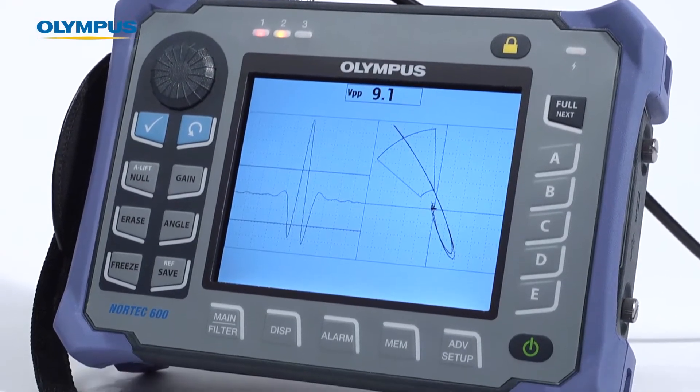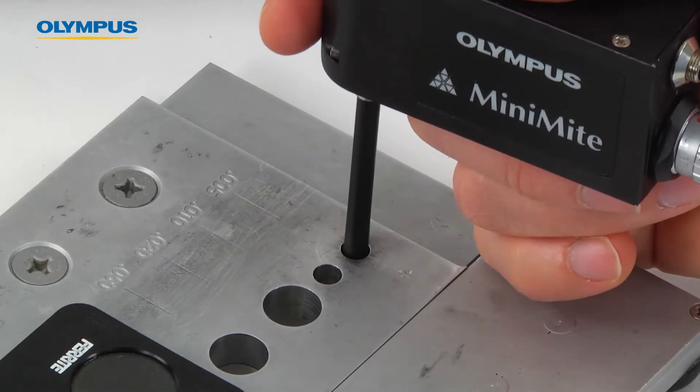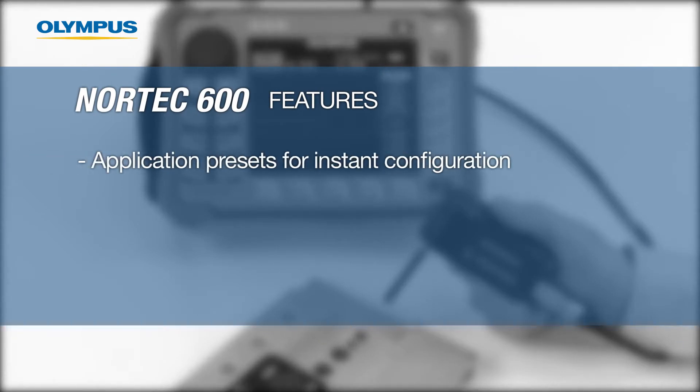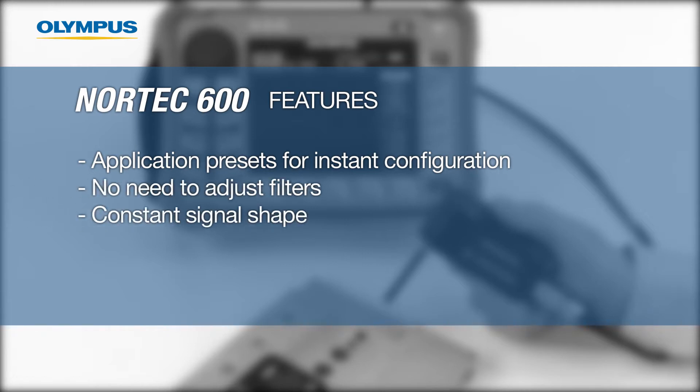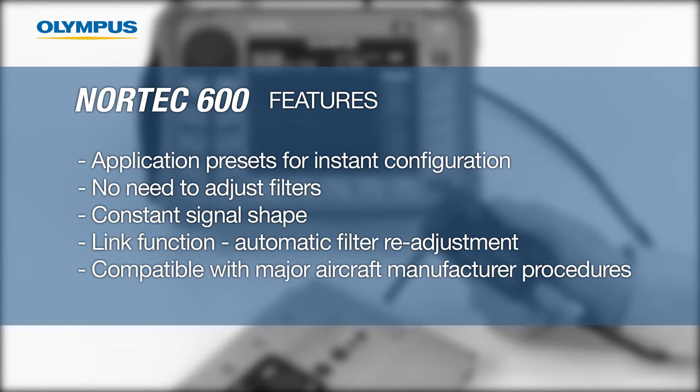This video will demonstrate how to configure the Nortec 600 for fastener hole inspection. The Nortec 600 offers several distinctive features: a menu of application presets so you can configure the instrument with the push of a button, no need for filter adjustment, new filter settings that ensure constant figure 6 and figure 8 signal shapes, a link function that automatically readjusts filter settings to compensate for changes in RPM control, and compatibility with all major aircraft manufacturer procedures.